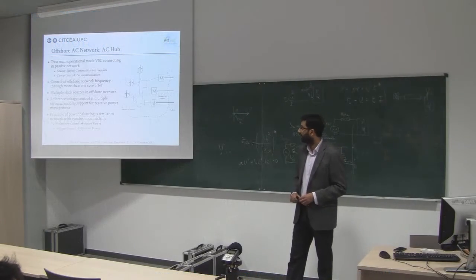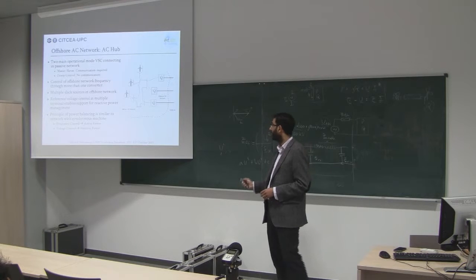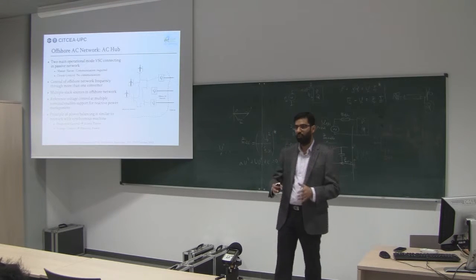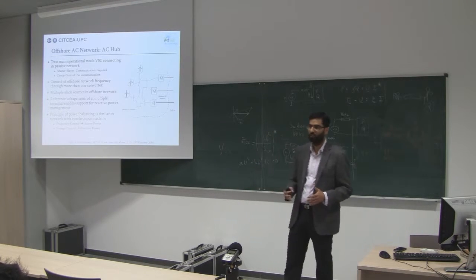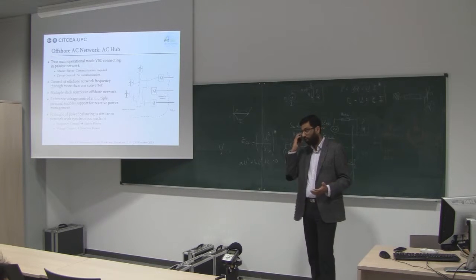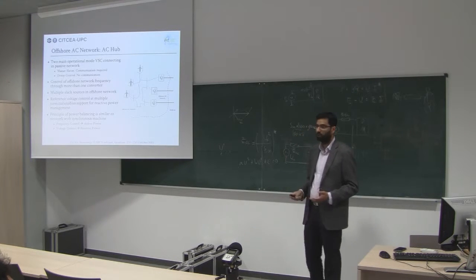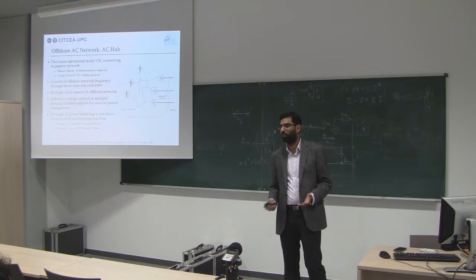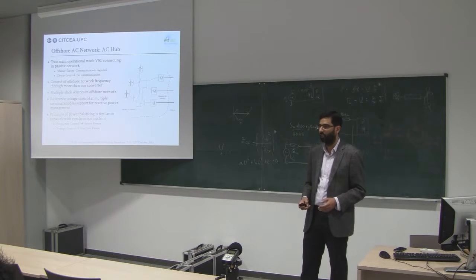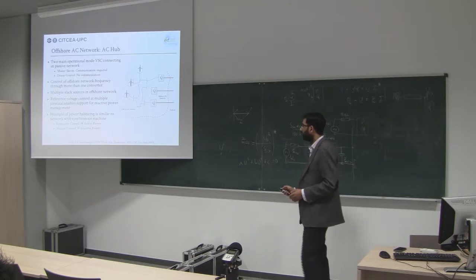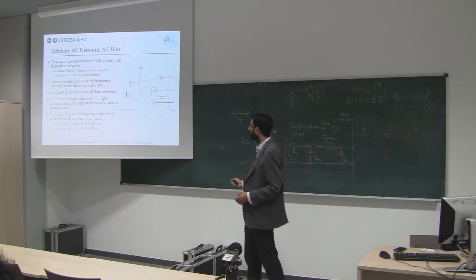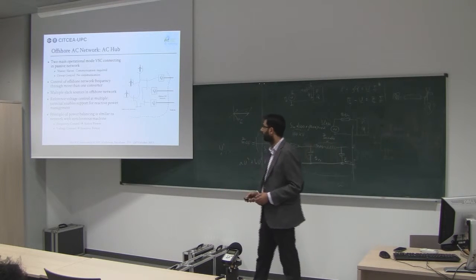The second method is called droop control method. In this method, all the converters are providing the frequency and they work as a synchronous machine to the network. So if one converter goes out, others will automatically control the frequency and the system can remain in operation. In this method, we can have multiple slack sources in the offshore network, controlling frequency with more than one converter.